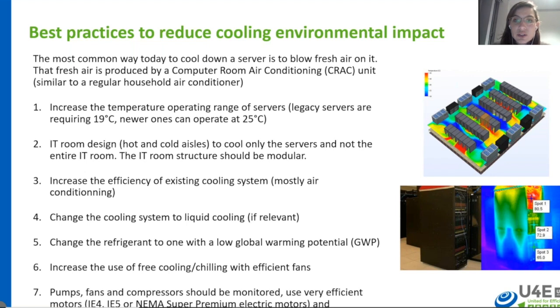The next one is to change the refrigerant to one with a low global warming potential. We recommend that the GWP of the refrigerant used in data center cooling equipment should be lower than 10, and for air conditioning equipment, lower than 680, just to have an idea.